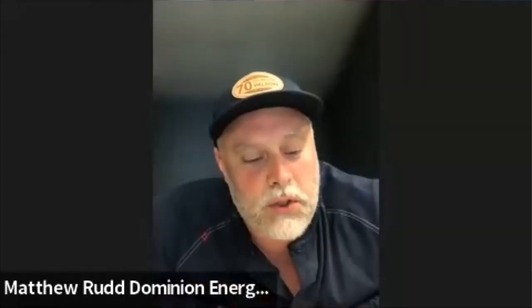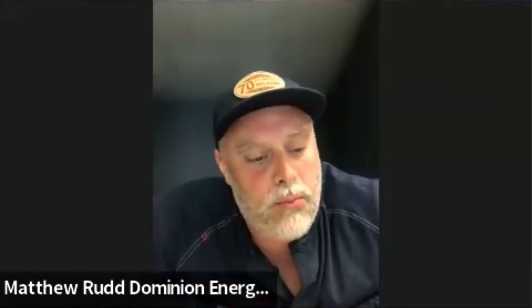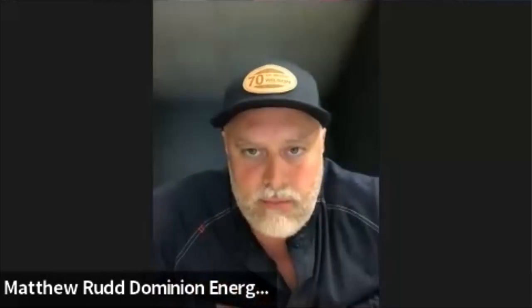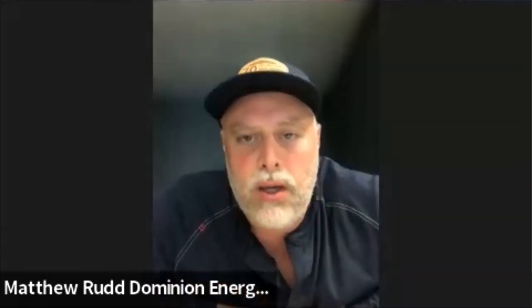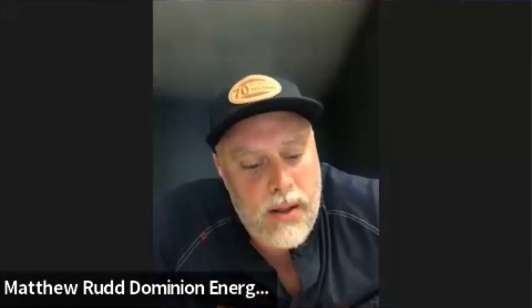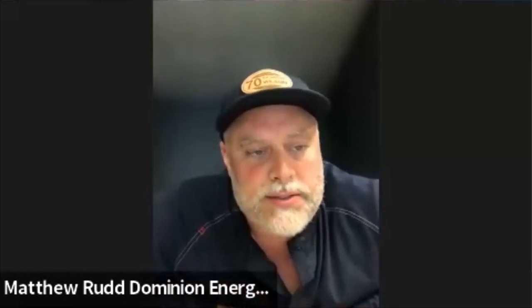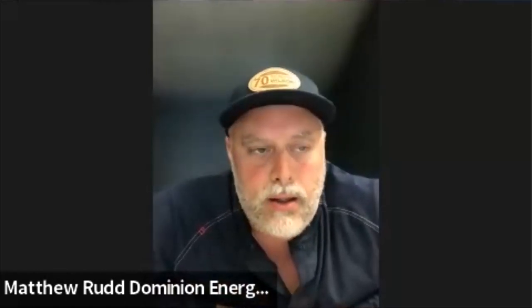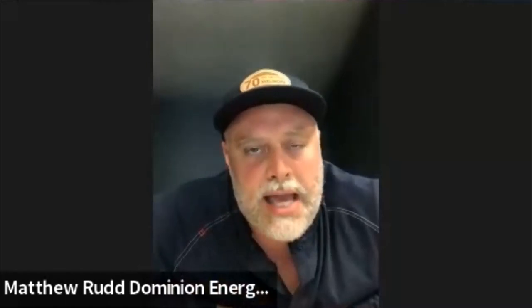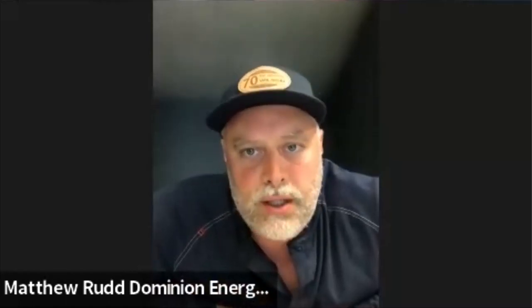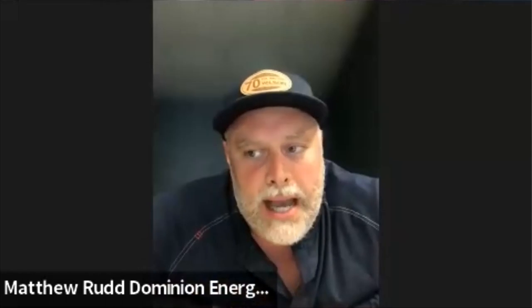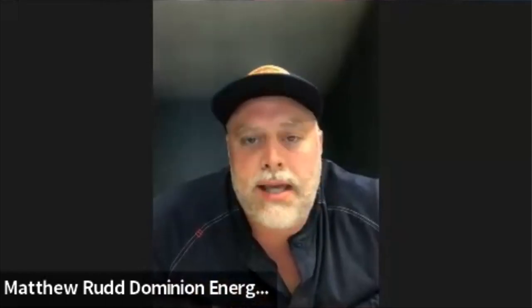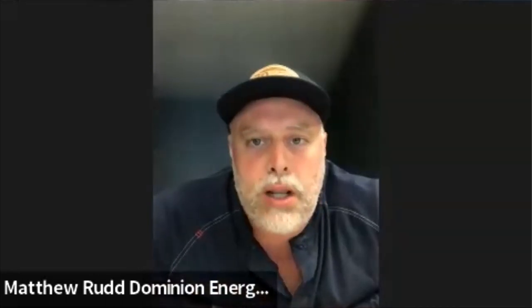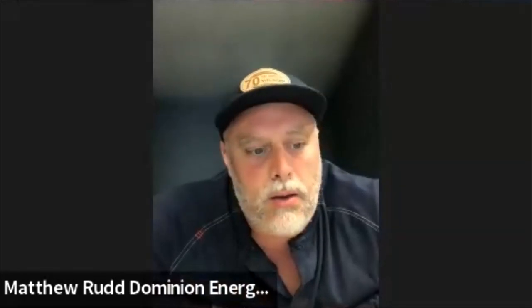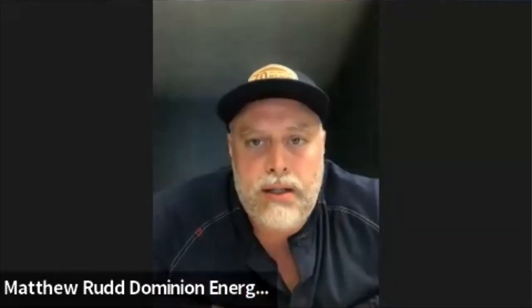Sure, the quickest way I can describe it: these transmission level voltages, 69 kV all the way up to 230 kV on our system, are designed with a thermal rating. These things are put in service to last 30, 40 years before you reconductor them. The quickest way I can describe it to anyone is it's like putting on a winter coat and going out in the summertime. That steel casing would have derated the line.